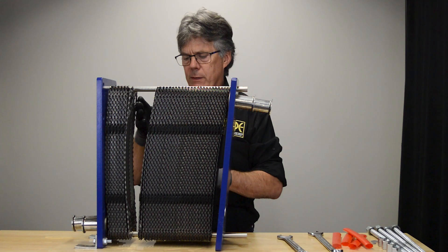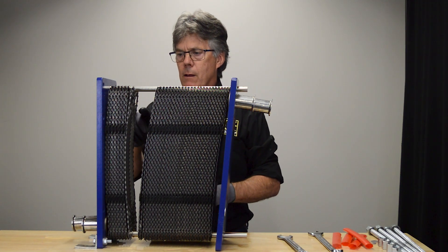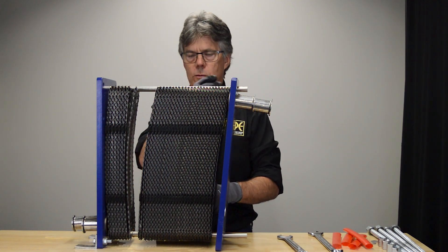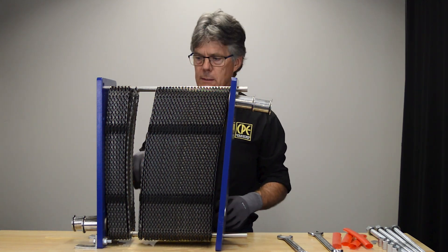So this one's going to have, it's a five pass, it's going to have one pass come here, one blocked plate, then over and blocked again, and then blocked again. So it's going to have four block plates, so we get five passes in here.